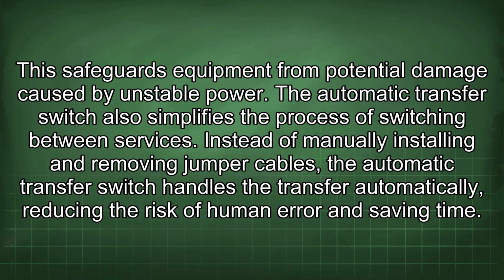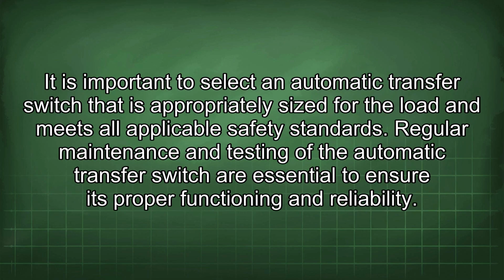The automatic transfer switch also simplifies the process of switching between services. Instead of manually installing and removing jumper cables, the automatic transfer switch handles the transfer automatically, reducing the risk of human error and saving time. It is important to select an automatic transfer switch that is appropriately sized for the load and meets all applicable safety standards. Regular maintenance and testing of the automatic transfer switch are essential to ensure its proper functioning and reliability.